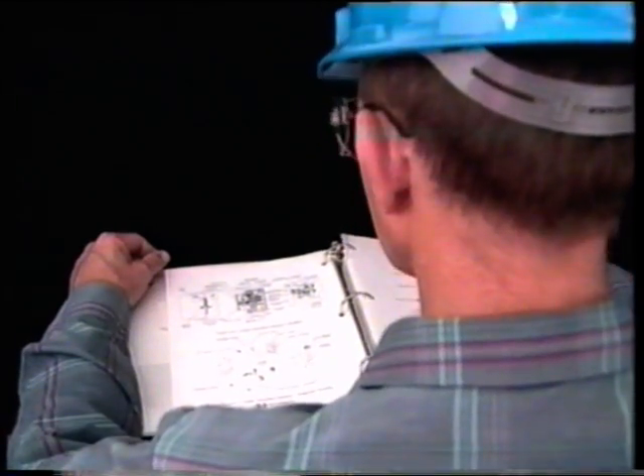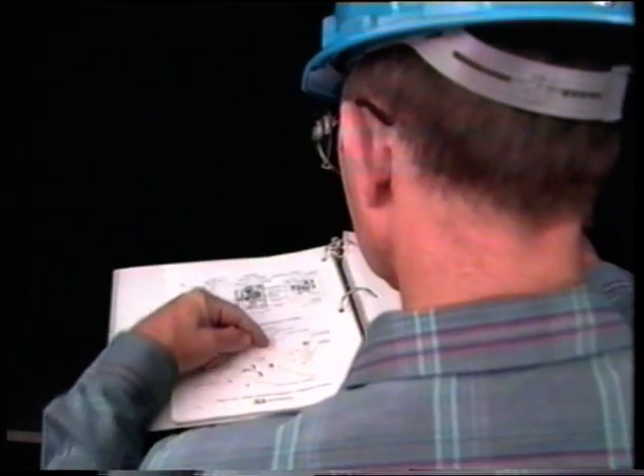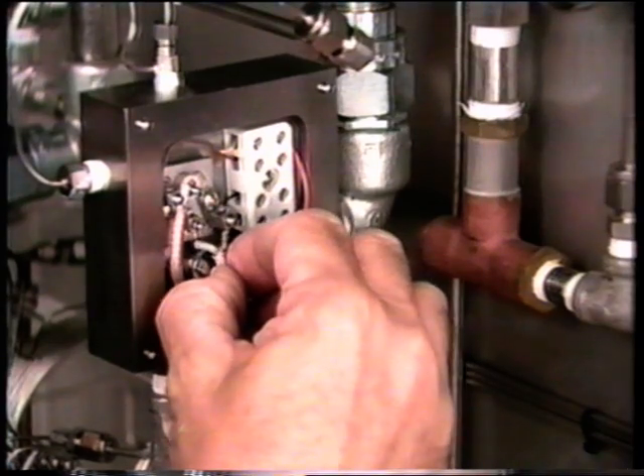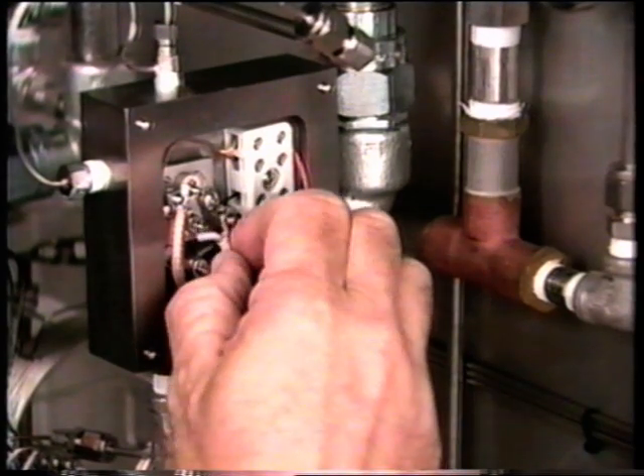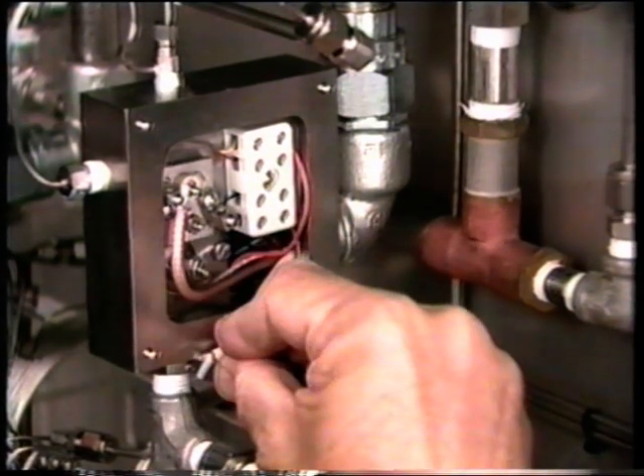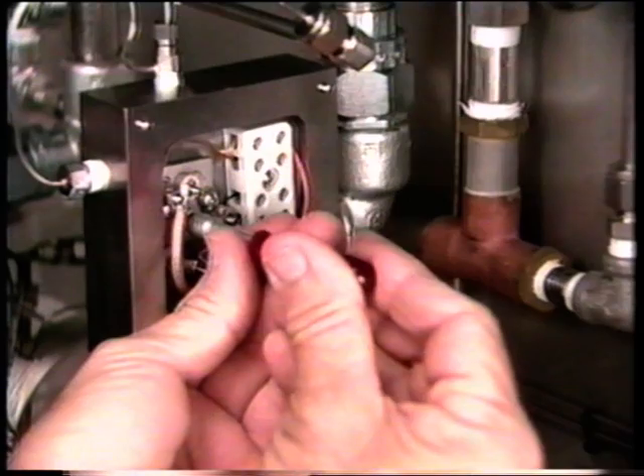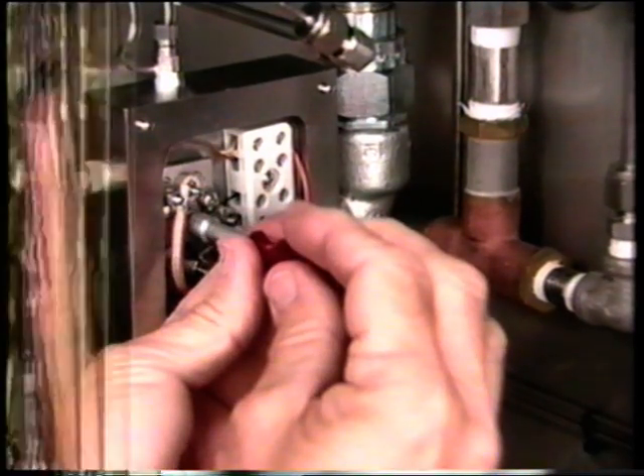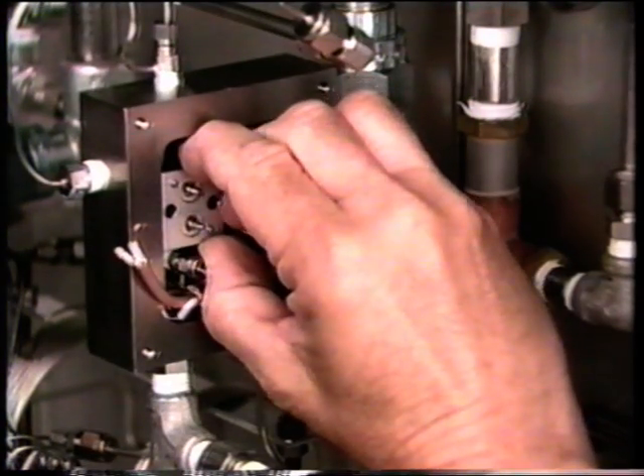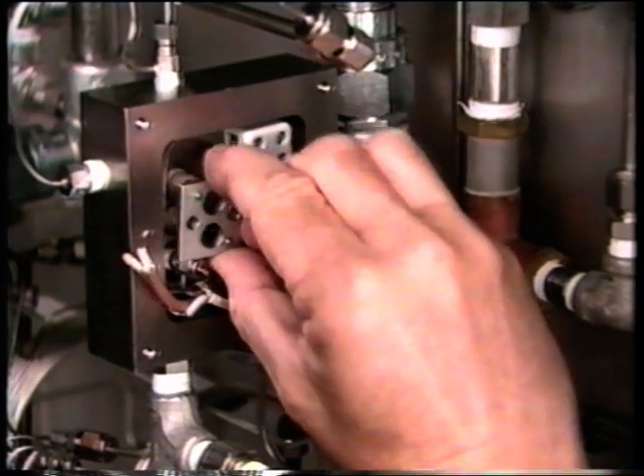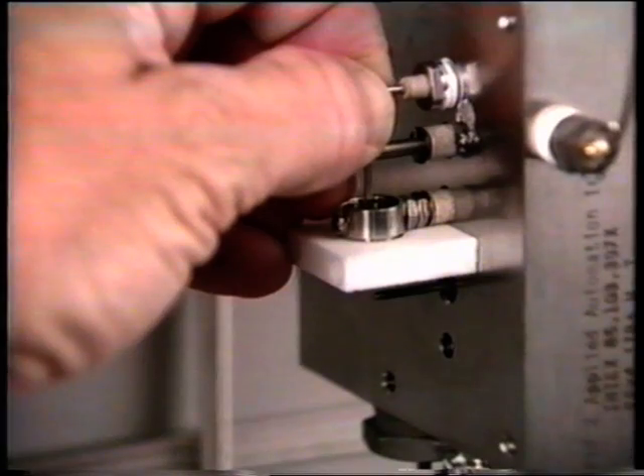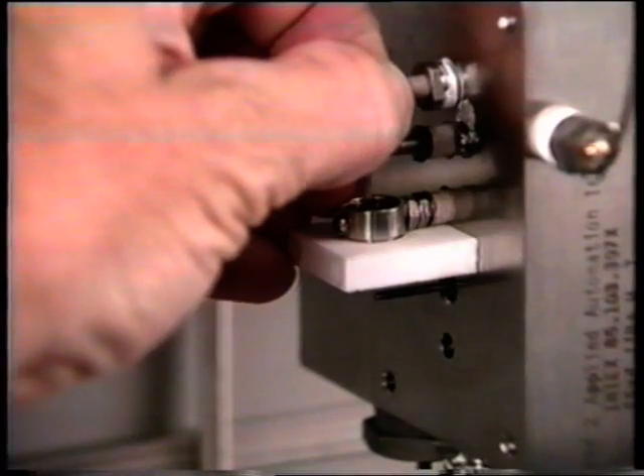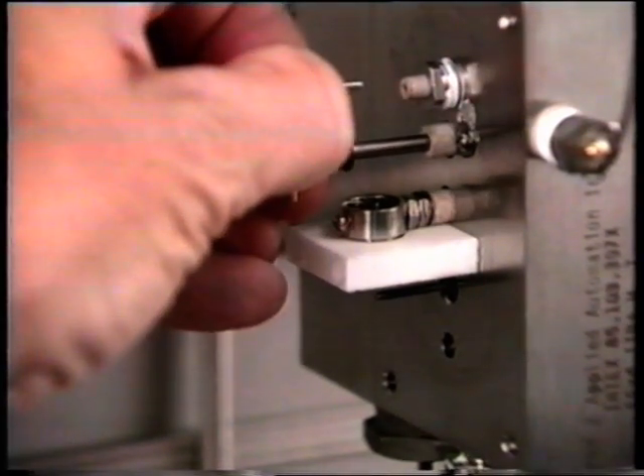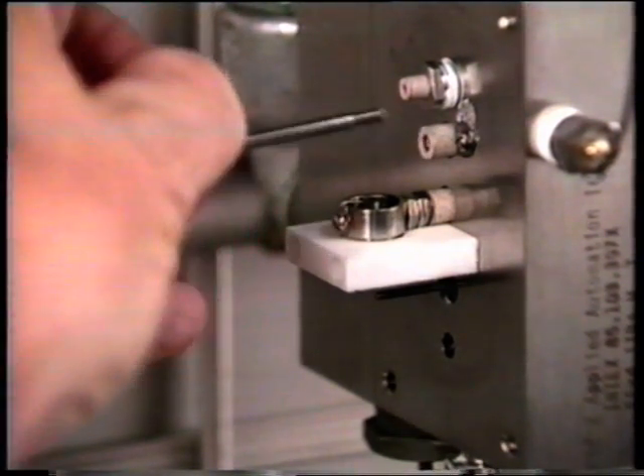Sometimes it will be necessary to replace the bias ignite and collector insulators. To do this, begin by removing the bias ignite and signal cables from their electrodes. Remove all nuts and washers from the electrodes. Remove the bias ignite and collector ground clamps and lift off the insulator clamp plate. Loosen the burner clamp nut. Loosen the bias ignite electrode and pull out both the burner tip and the bias ignite electrode.